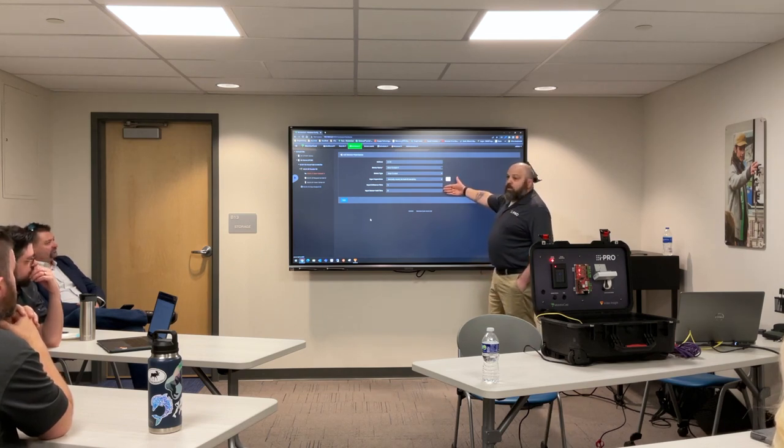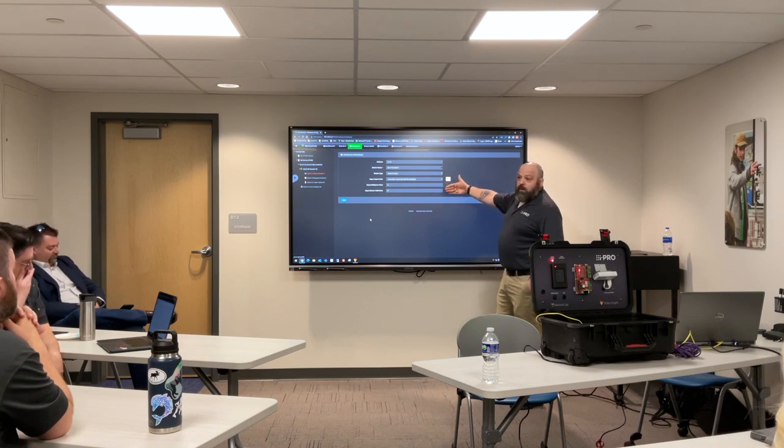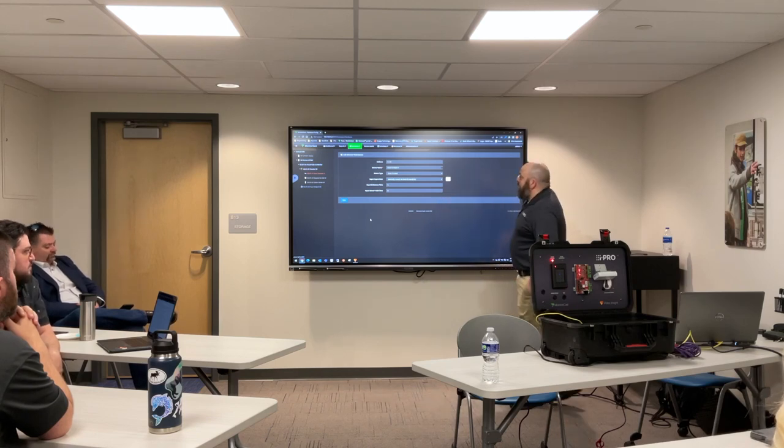Yeah, like whether the door just kind of rattles enough that it causes a whole bunch of false alarms. If you ever do have that, we can set up a debounce time to say it has to be so long before it triggers an alarm. Sensor hold time is going to be a delay before it triggers the alarm. So if you want to say they can open the door and shut it again, we can set that up.